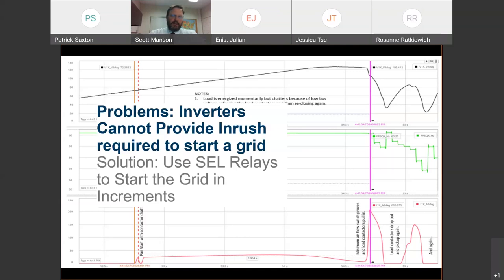Okay, back to the point that I've made several times. Inverters' current behaviors aren't the same as your traditional power systems designed by Nikola Tesla and others over 100 years ago. These inverters don't produce the magnitude or the time sequenced current or voltage behaviors we expect. As an example, let's take a little thought exercise, one that I think is a light bulb moment for us all. If you have an islanded microgrid and you have a large battery sized for your load, we'll call that size of load, whatever the units are, one. That inverter can produce only one current. It can't produce two, it can't produce three.